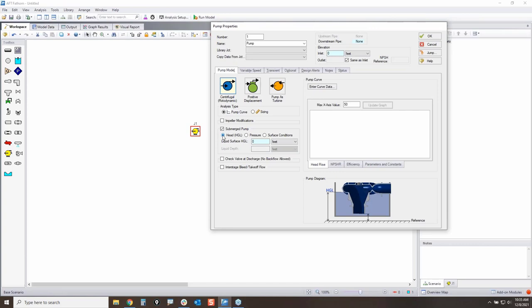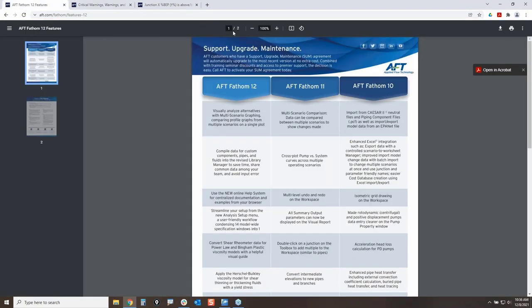Hydraulic grade line was a little bit more tricky in the past because the value that you're supposed to specify here is the actual true elevation of the liquid surface level that your pump is submerged in. And so that's the reference that you would need to use for that. I wrote a blog article on it that you can find.